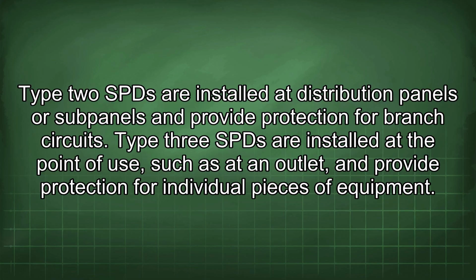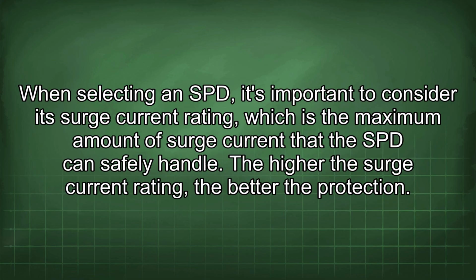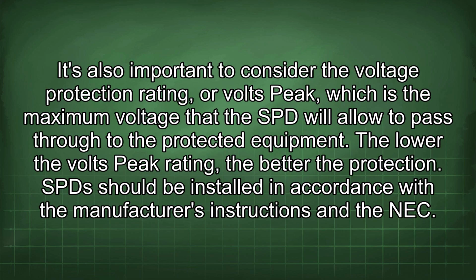pieces of equipment. When selecting an SPD, it's important to consider its surge current rating, which is the maximum amount of surge current that the SPD can safely handle. The higher the surge current rating, the better the protection. It's also important to consider the voltage protection rating, or volts peak, which is the maximum voltage that the SPD will allow to pass through to the protected equipment.